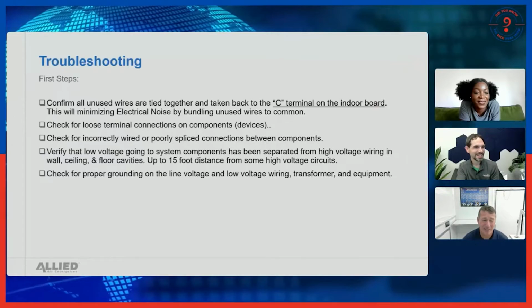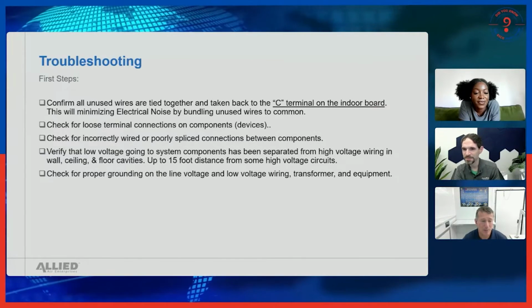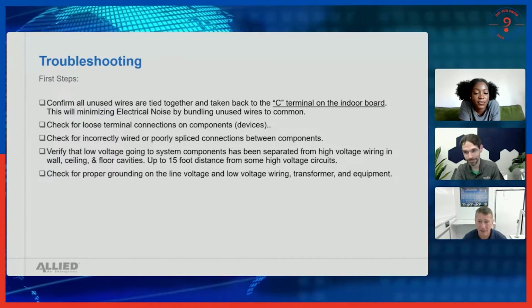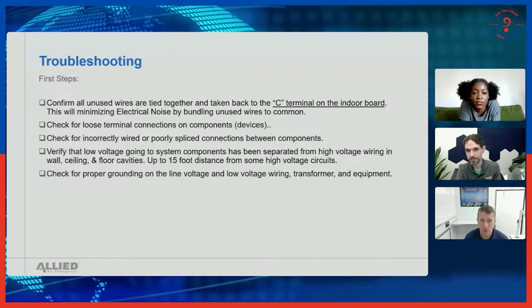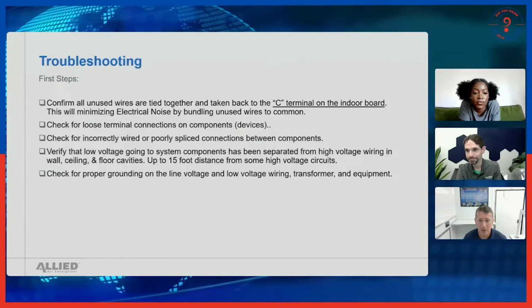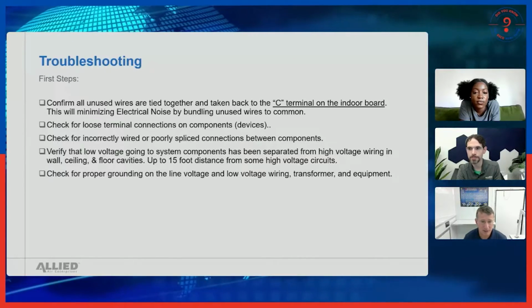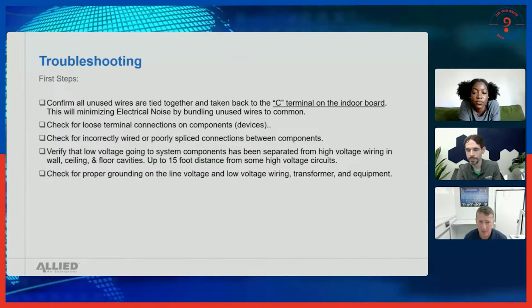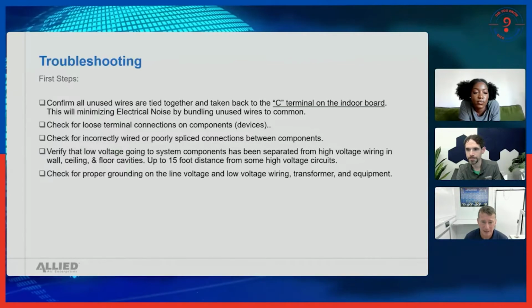Yeah, that's perfect. That's actually one of the larger components of failures I've found in the industry. I always recommend running new thermostat wire if we can when doing an installation on a communicating system, but many times we can't, and we're reusing the existing thermostat wire.